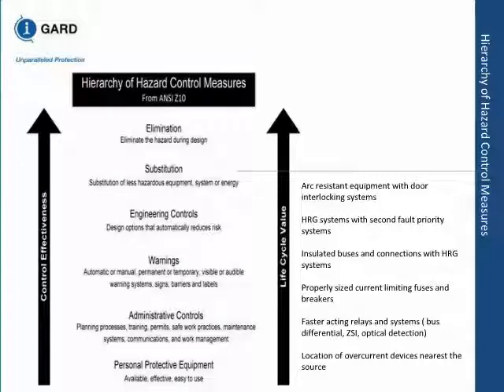Okay? Then you have faster acting relays, for example bus differential, zone selective interlocking, optical detection. Okay? Or you can consider the location of the overcurrent device. When you have a transformer and you have a 10-foot bus duct or cable, the main breaker has the highest incident energy when the fault happens line side. You could probably put your CTs on the transformer bushing and trip the upstream device.